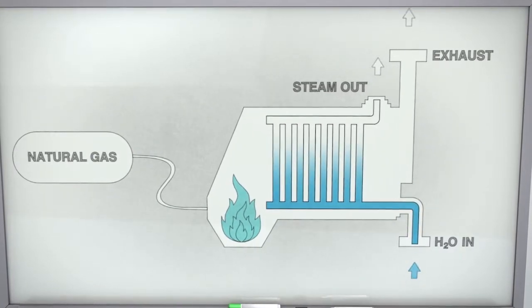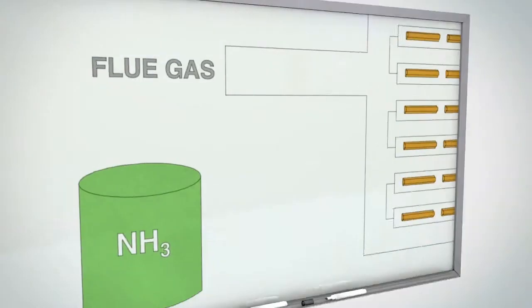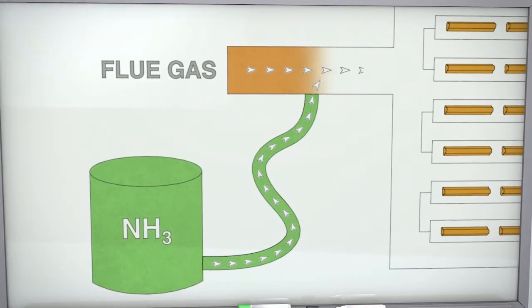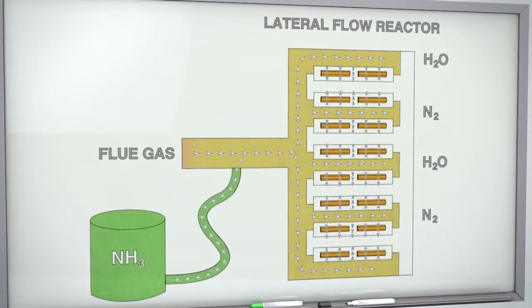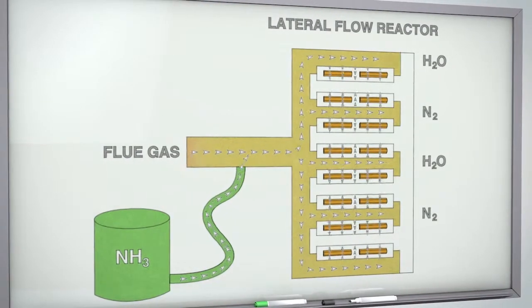In order to reduce these emissions, the Shell-DNOx system begins by injecting ammonia into the flue gas stream. The mixture then travels over a CRI high-activity catalyst located in the lateral flow reactor, or LFR.